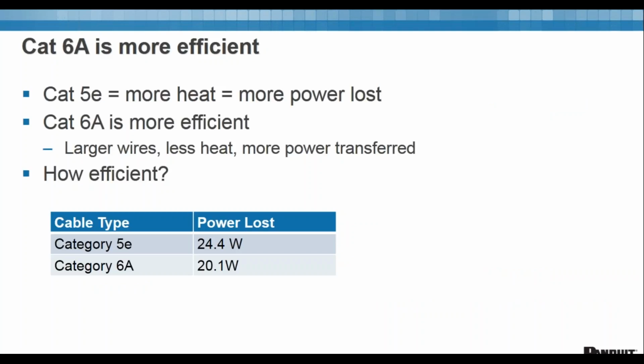The last way to say Category 6A is more efficient: 5E cables get hotter. Why do they get hotter? They generate more heat, meaning more power is lost. Heat's coming from somewhere. Category 6A is more efficient. It has larger wires, therefore less heat is lost. A lot of 5E cables these days use 24 gauge wire. A 6A cable is 23 gauge wire. And even comparing 6A to 6, usually 6A cables use a larger 23 gauge wire than a Cat 6. So when you get down to it, for that same amount of cable, a Category 6A system will use about 4 watts less power.